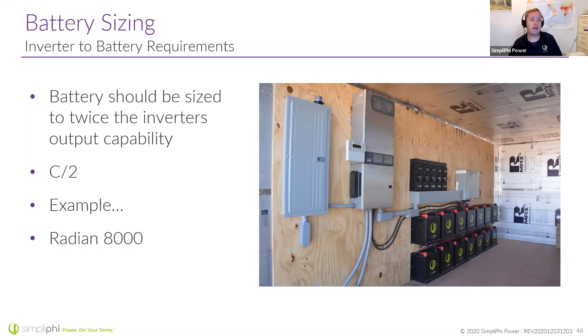Don't charge or discharge faster than what we're capable of. On the DC to DC side, I see a bunch of these Outback charge controllers here. It's a little easier because we can tell a charge controller to limit its charge amps, so I'm not as concerned about that. But when it comes time to sizing these inverters, always keep in mind, the battery should be sized twice the inverter's output capabilities, unless you're using these SimpliPhi batteries.